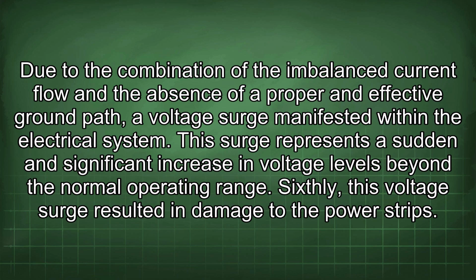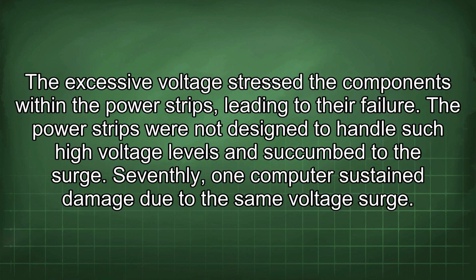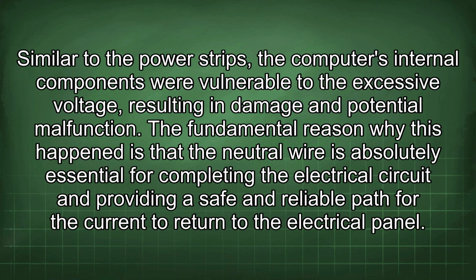Sixthly, this voltage surge resulted in damage to the power strips. The excessive voltage stressed the components within the power strips, leading to their failure. The power strips were not designed to handle such high voltage levels and succumbed to the surge. Seventhly, one computer sustained damage due to the same voltage surge. Similar to the power strips, the computer's internal components were vulnerable to the excessive voltage, resulting in damage and potential malfunction.